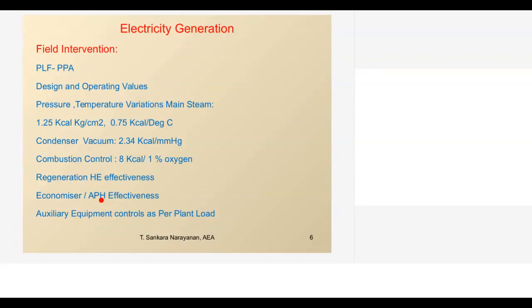Then economizer and air preheater, again both are heat exchangers. This one is gas to water, this one is gas to air. Sometimes there may be an issue in the air preheater itself. If we are not able to get the designed preheat temperature, then automatically the overall heat rate will increase. See, these are all the points. Then auxiliary equipment controls as per the part load.